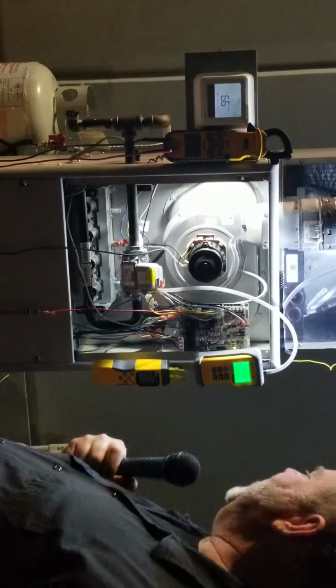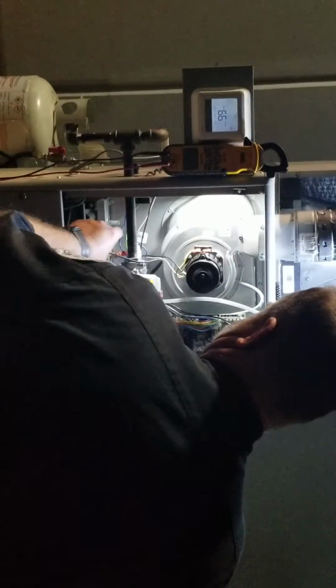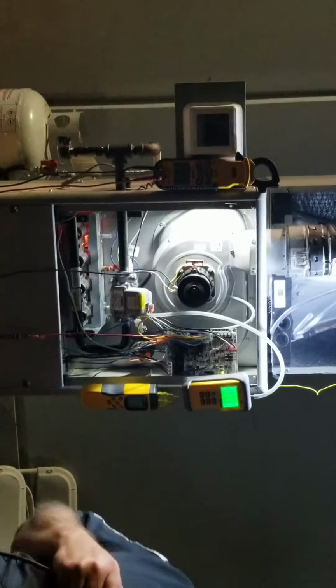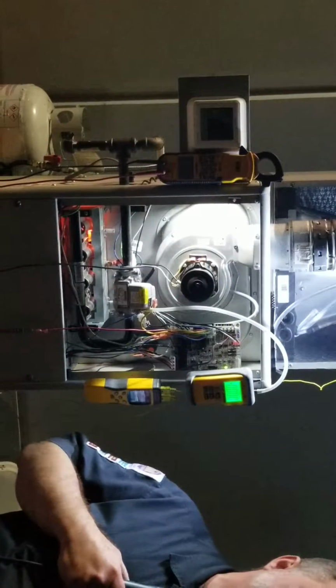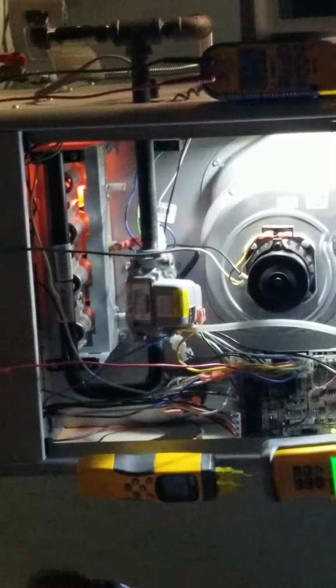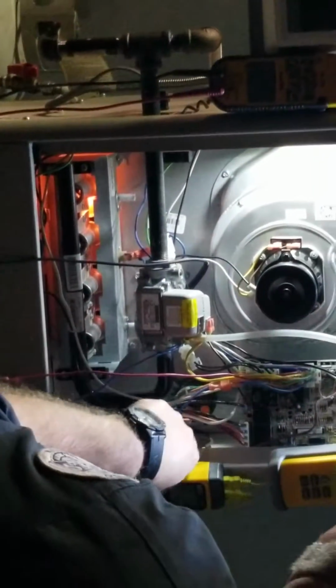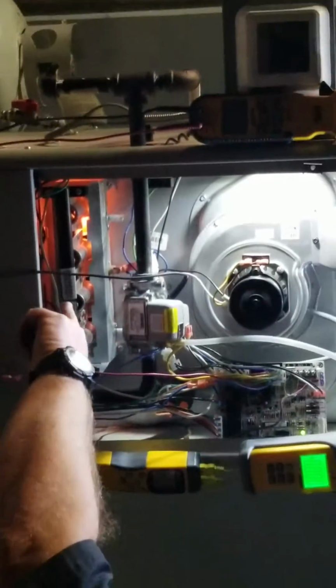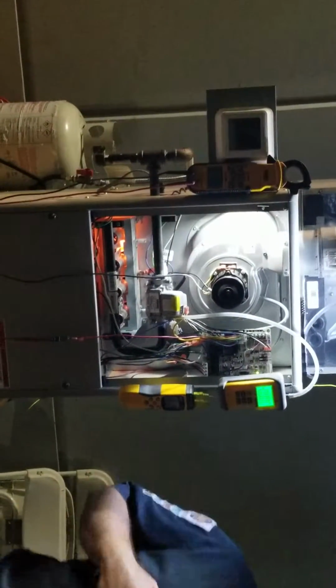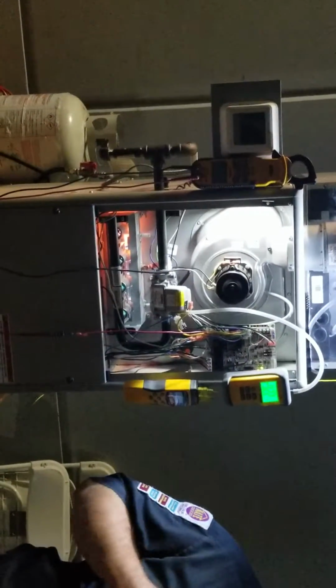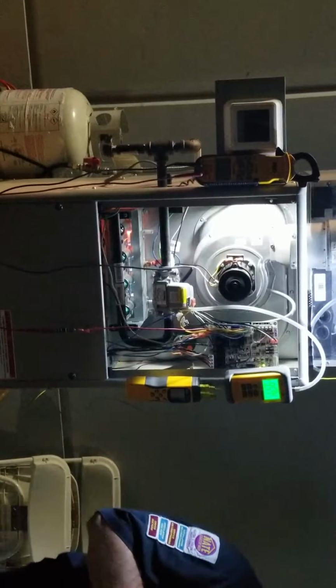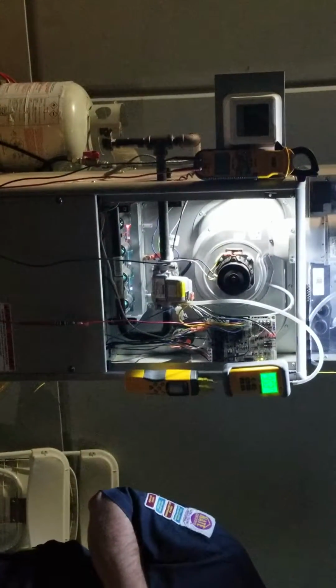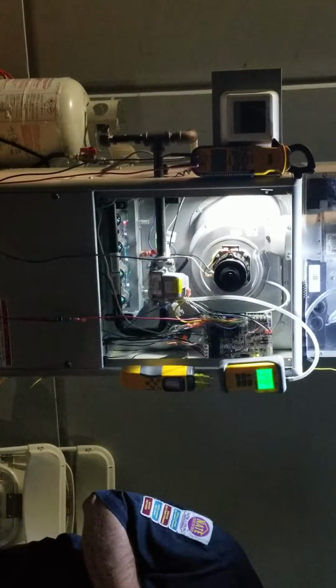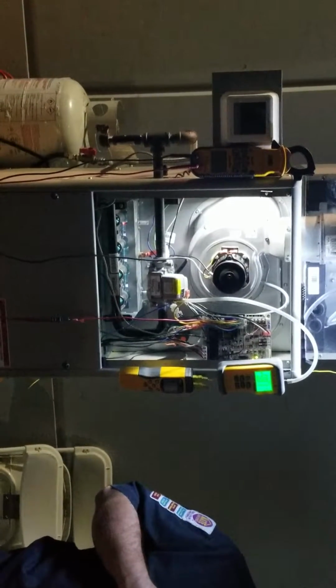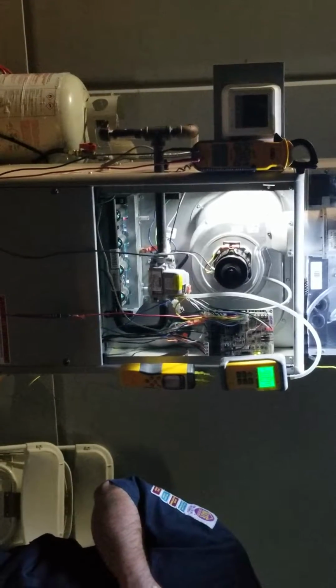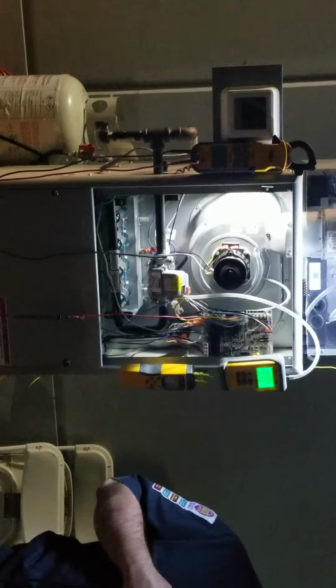Okay, the very first thing that happened is the inducer fan motor started. So that means that our switch was open at first, right? And now the pressure switch has to close, or our hot surface igniter does not come on. So if a hot surface igniter does not come on, we need to check to see if that pressure switch is closed, right? Because we saw our sequence of operation, right? So it did close, obviously, and it lit, and it went all the way across.